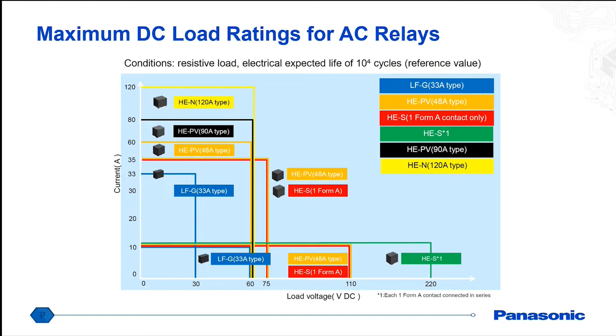So I just want to go into a little bit more detail about the HE-S relay. What's interesting about this one is the contact arrangement. It actually has two normally open contacts as well as a normally closed auxiliary contact. The purpose of that auxiliary contact is that you can monitor the normally open contacts for welding and design a safety circuit around it. Also, this relay features a very low coil holding voltage, so it doesn't use up a whole lot of power. Once the relay is energized, you can reduce the coil voltage so that it's only using up 170 milliwatts of power.